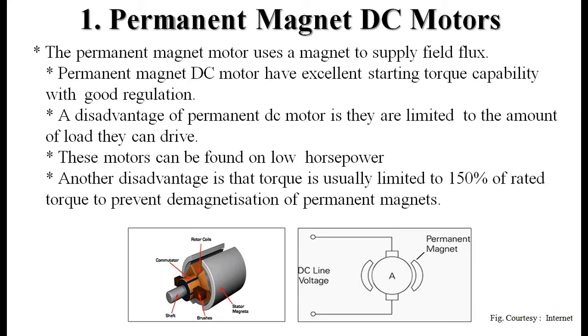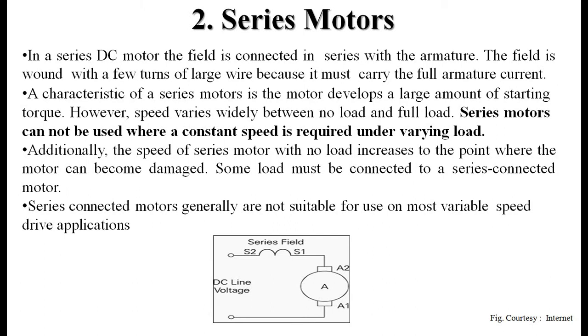The next type is the series DC motor. In a series DC motor, the field is connected in series with the armature. A1-A2 are the brushes, and S1-S2 is the coil in series with the armature winding. The field is wound with a few turns of large wire because it must carry the full armature current. A series motor develops a large amount of starting torque; however, speed varies widely between no-load and full-load conditions.